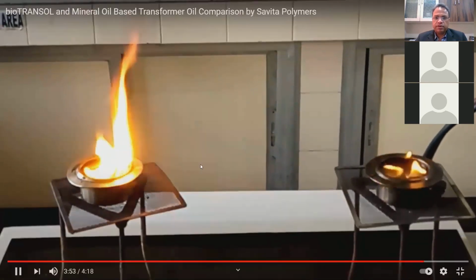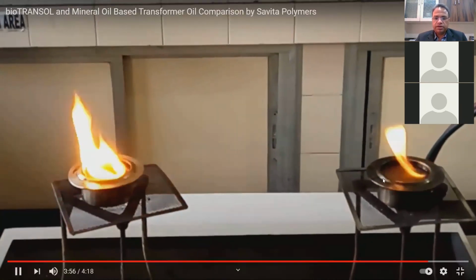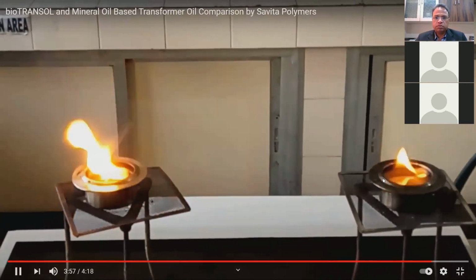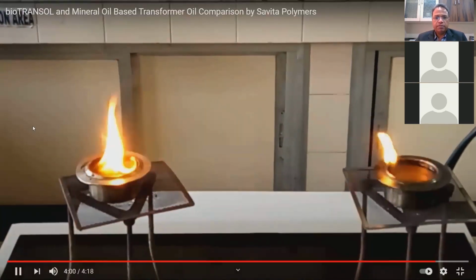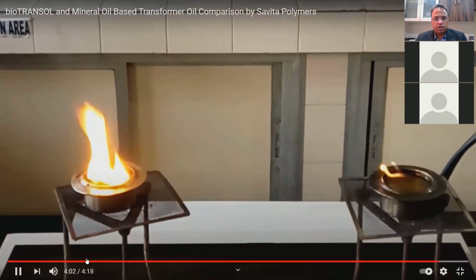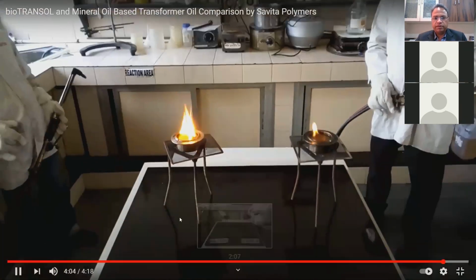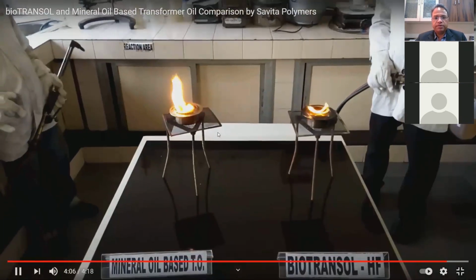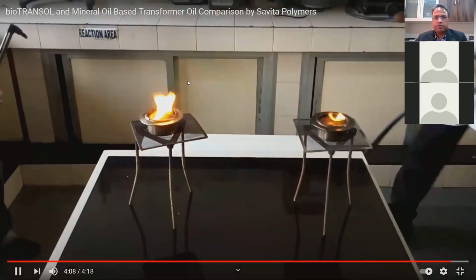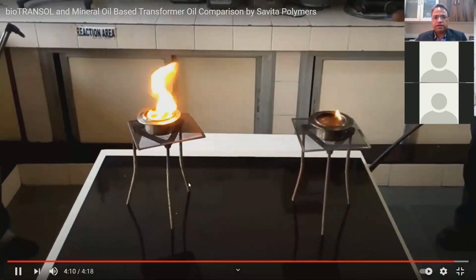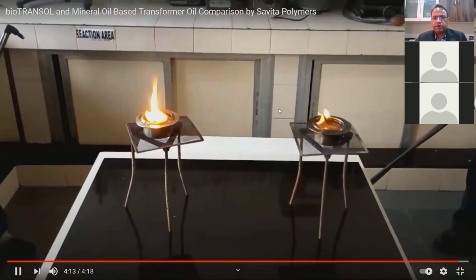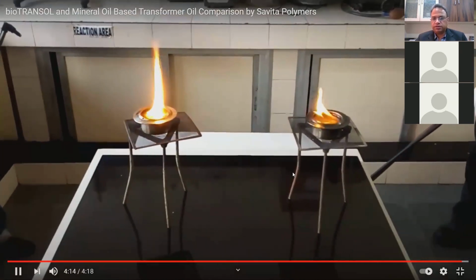So now you see both are burning, but ester is burning at a very slow, low intensity, while mineral oil, even after 4 minutes, is still burning at the same intensity. So mineral oil is more dangerous as far as the fire safety is concerned compared to synthetic or natural esters.